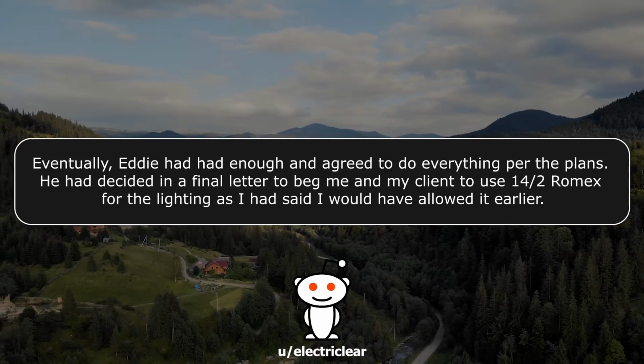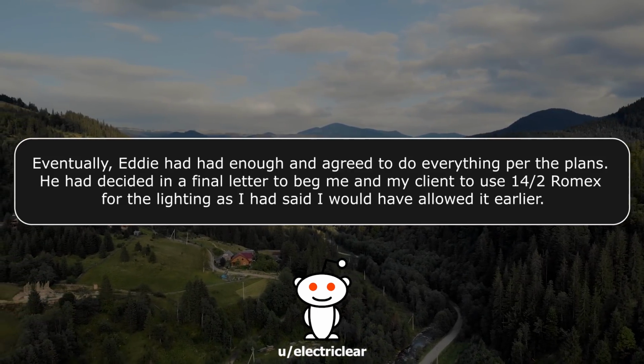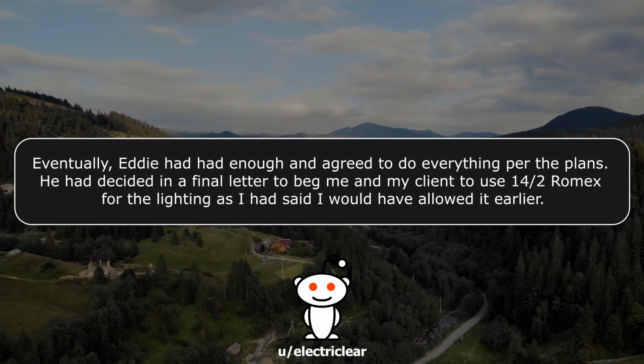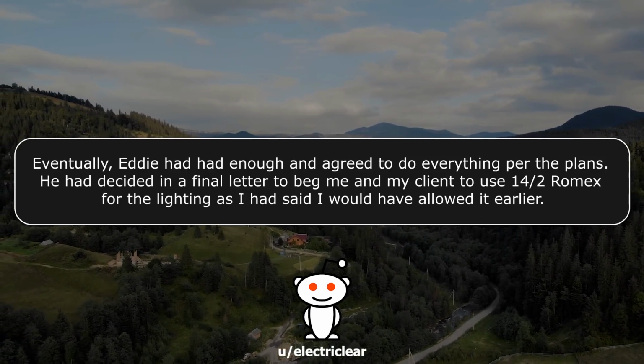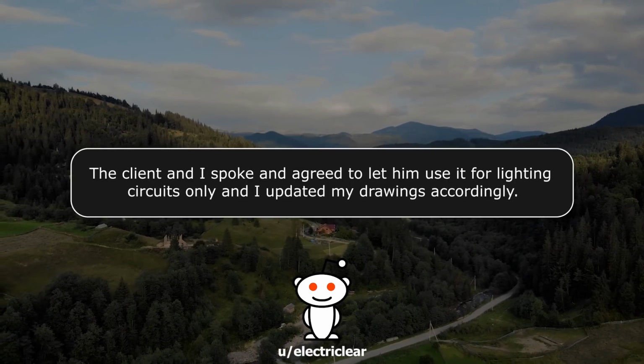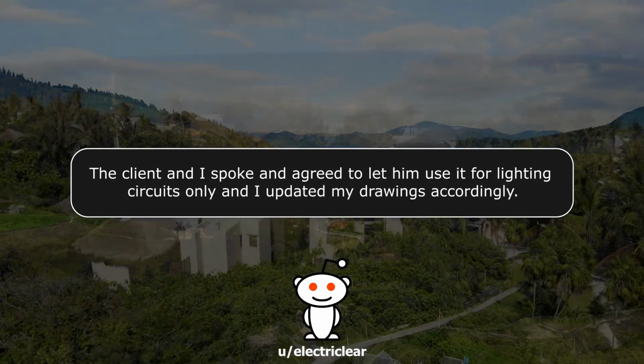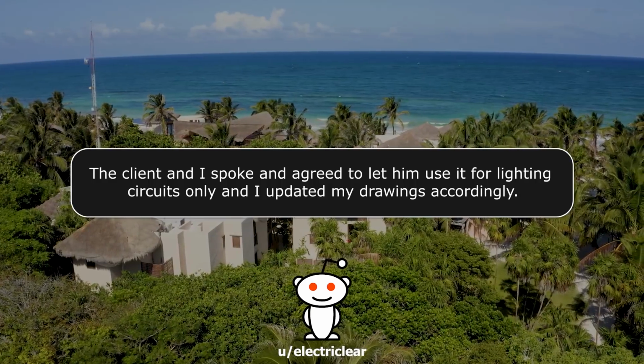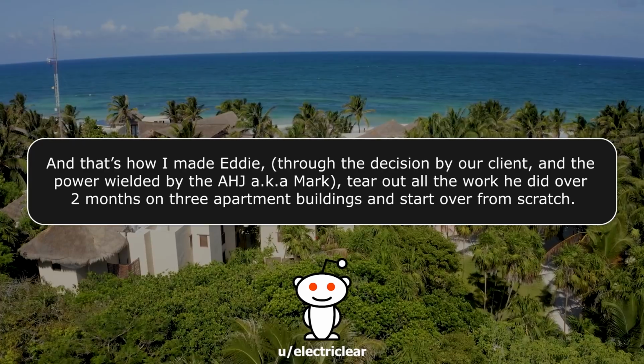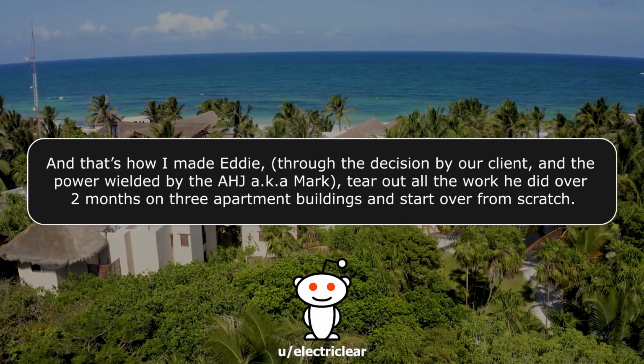Eventually, Eddie had had enough and agreed to do everything per the plans. He had decided in a final letter to beg me and my client to use the 14-2 Romex for the lighting, as I had said I would have allowed it earlier. The client and I spoke, and we agreed to let him use it for lighting circuits only, and I updated my drawings accordingly.